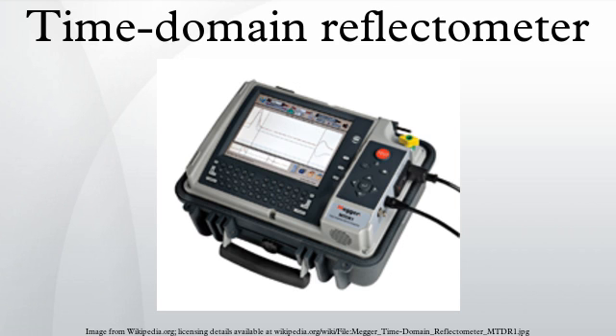Time domain reflectometers are commonly used for in-place testing of very long cable runs, where it is impractical to dig up or remove what may be a kilometers-long cable. They are indispensable for preventive maintenance of telecommunication lines, as the TDR can detect resistance on joints and connectors as they corrode, and increasing insulation leakage as it degrades and absorbs moisture, long before either leads to catastrophic failures. Using a TDR, it is possible to pinpoint a fault to within centimeters.